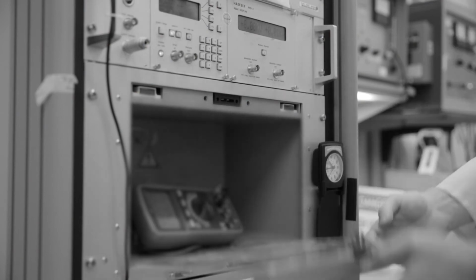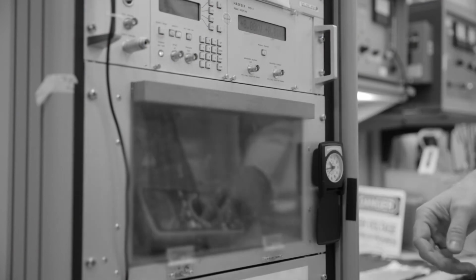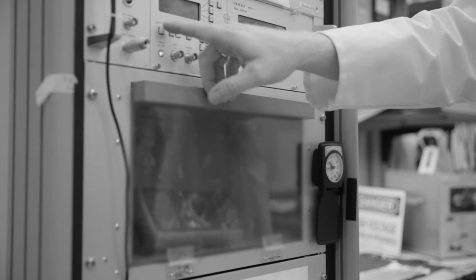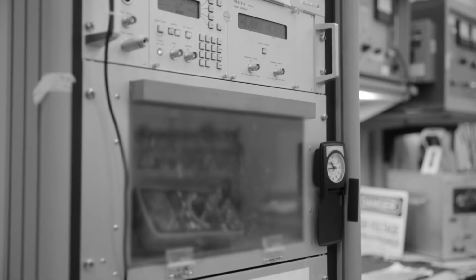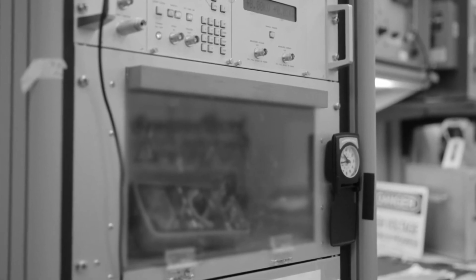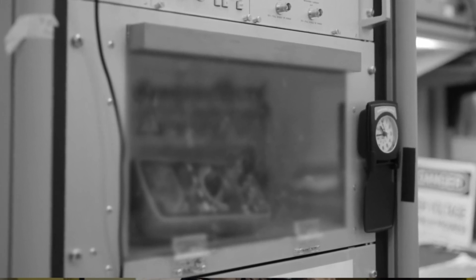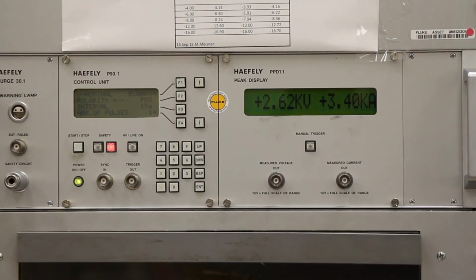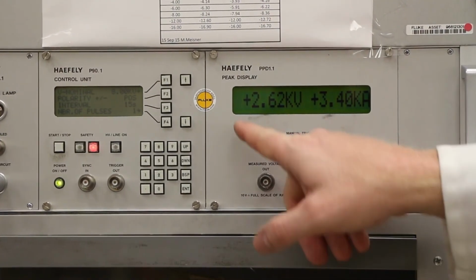In a Cat 3 or a Cat 4 environment when connected to the mains, the arc would be fueled with thousands of amps. The resulting arc flash could cause serious damage to people and equipment. Here's what happened at Fluke Labs when an off-the-shelf meter marked Cat 4 600 volt is hit with 8,000 volts of transient energy. It failed at only 2.62 kilovolts.